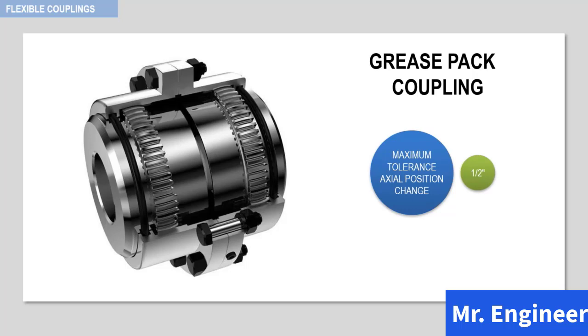There is a common disadvantage in all gear type flexible couplings. Any gear mesh has a breakaway friction factor in the axial direction, caused by the high contact force between the two sets of gear teeth. The result is that the forces imposed on the driver and driven shafts are not totally predictable, and are sometimes higher than desired due to the quality of the tooth machine surfaces and the inevitable build-up of sludge or foreign material in the tooth mesh during extended service.